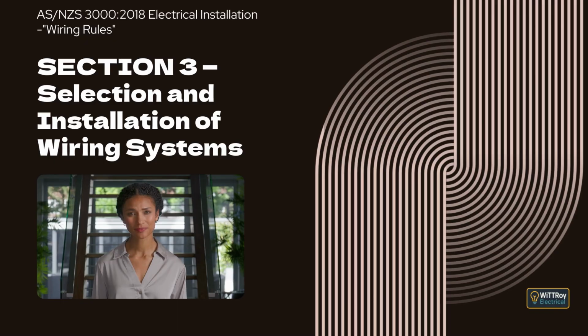Clause 3.3.2.5 Corrosive or polluting substances. This clause explains that where corrosive or polluting substances may cause deterioration, affected parts of the wiring system must be protected or made from materials that resist those substances. Metals that can cause galvanic action must not be placed in contact with each other. Materials that could cause deterioration or hazardous degradation must also not be placed together.